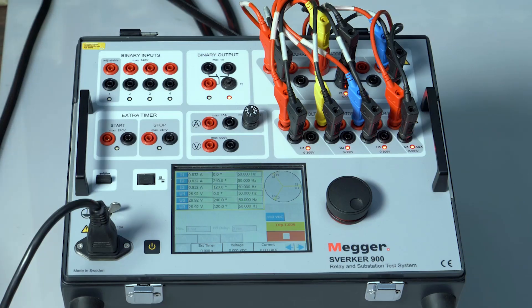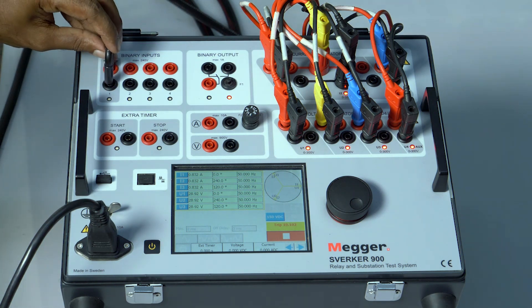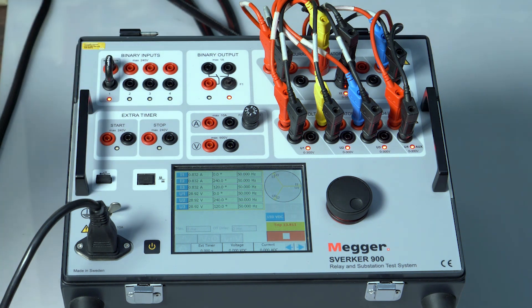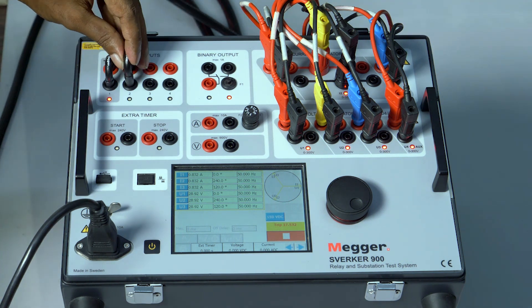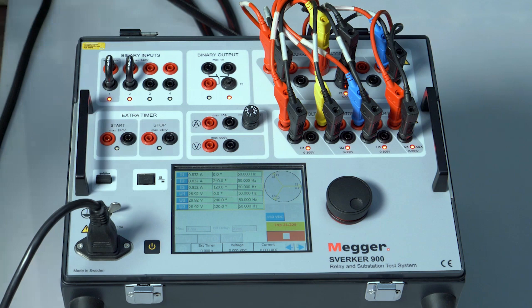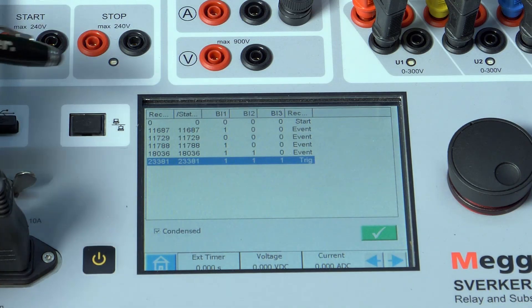You can see that the timing is running. Now I'm going to short the binary input 1 approximately at 11 seconds and binary input 2 at approximately 17 seconds and binary input 3. We can see that when all the three are shorted, it stopped injecting.